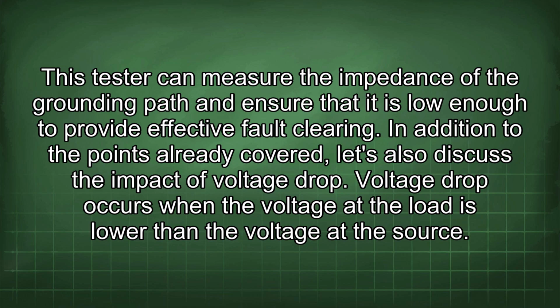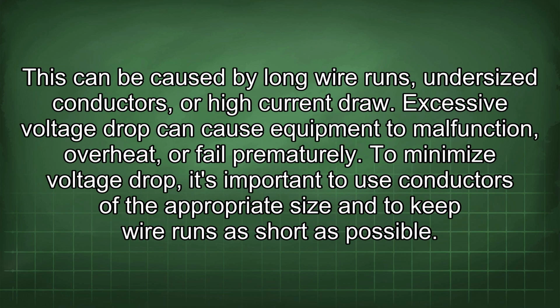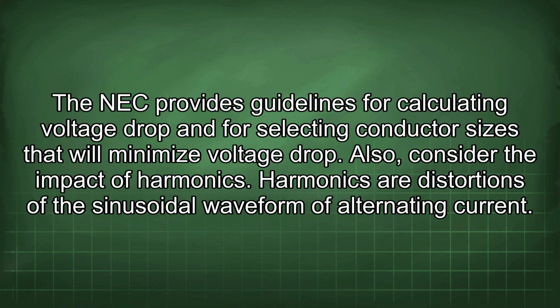In addition to the points already covered, let's also discuss the impact of voltage drop. Voltage drop occurs when the voltage at the load is lower than the voltage at the source. This can be caused by long wire runs, undersized conductors, or high current draw. Excessive voltage drop can cause equipment to malfunction, overheat, or fail prematurely. To minimize voltage drop, it's important to use conductors of the appropriate size and to keep wire runs as short as possible. The NEC provides guidelines for calculating voltage drop and for selecting conductor sizes that will minimize voltage drop.